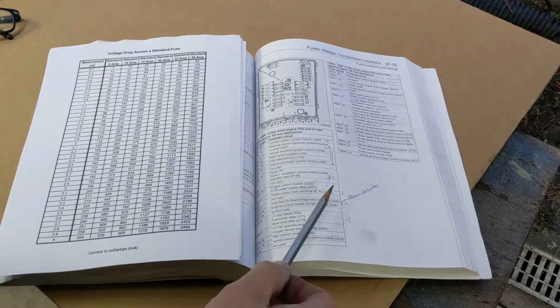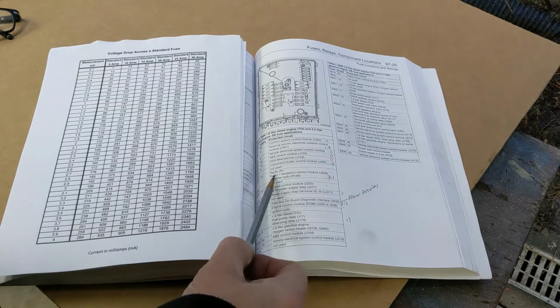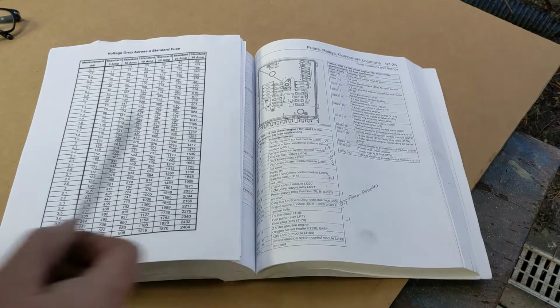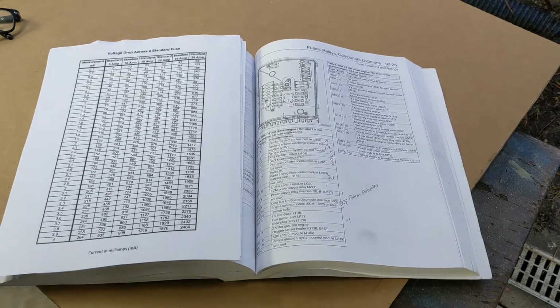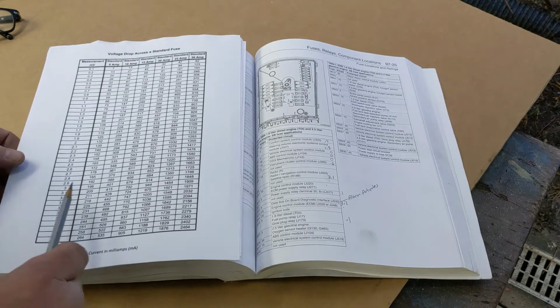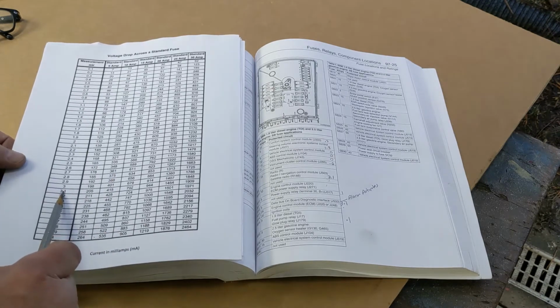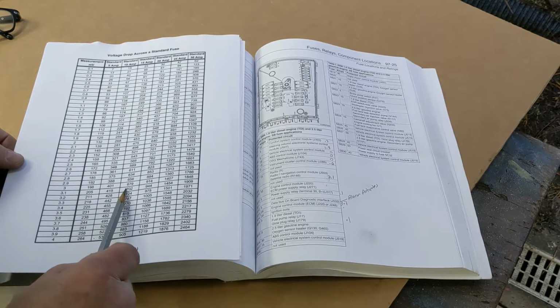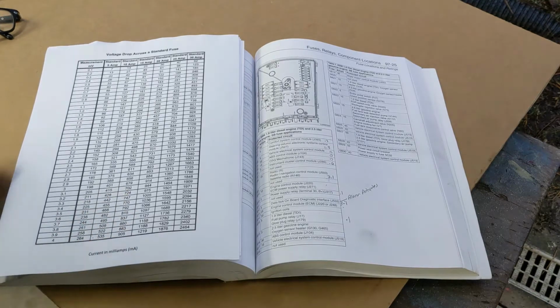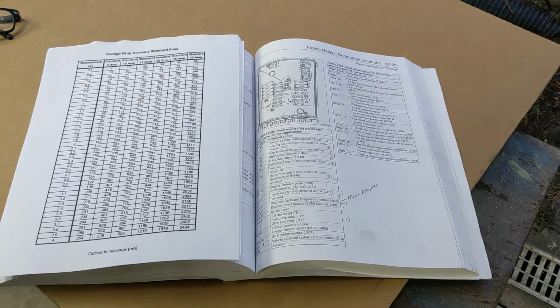So say, for instance, this one here, SB8, it's a 15 amp fuse. I recorded 3.1 millivolts across the fuse. You go over to this chart, find 3.1 millivolts, and read across to a 15 amp fuse, and that's 702 milliamps. That's about what I was reading when I pulled the fuse out and put my own amp meter in line with it. I was getting about 7/10 of an amp.